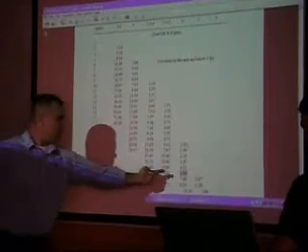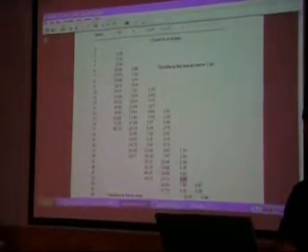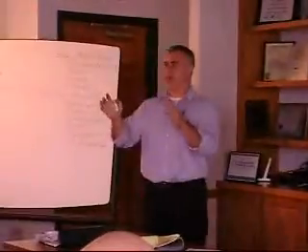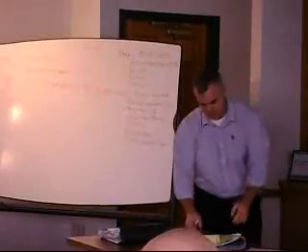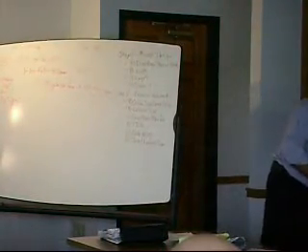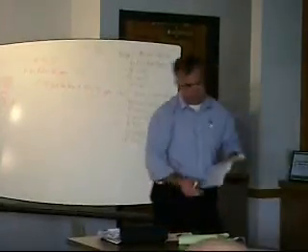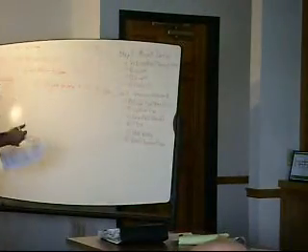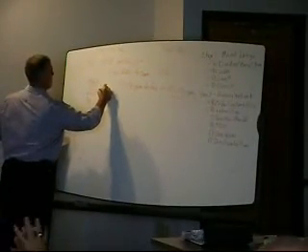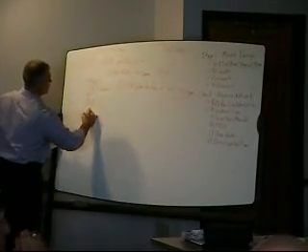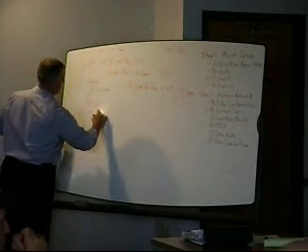Higher flow rate means it goes farther down the table, and it creates more friction in any type of pipe you use. So there's why you start seeing reasoning why you do certain things, because the end result is TDH and flow rate. All right, so we've chosen 2-inch for this scenario, and we could run through it, but we're not going to. This is 1.5 inch laterals and 2-inch force main. Okay.